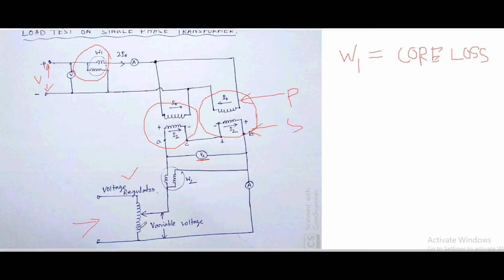Now when we inject the voltage by using this voltage regulator, due to this voltage a current will circulate through this secondary. Suppose this is the I2 current, which circulates here. This is the path. By using the voltage regulator, we can adjust this secondary current up to its maximum rated current. And when the maximum rated current flows through the secondary winding, at the same instant the primary will carry its rated current by transformer action.